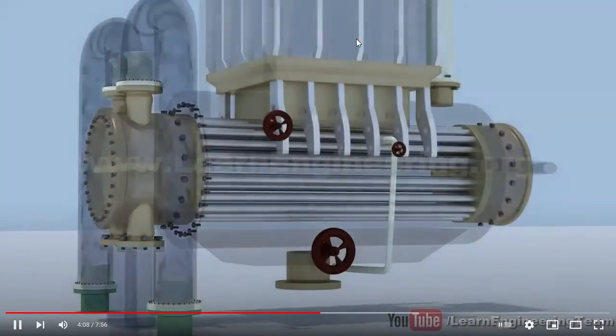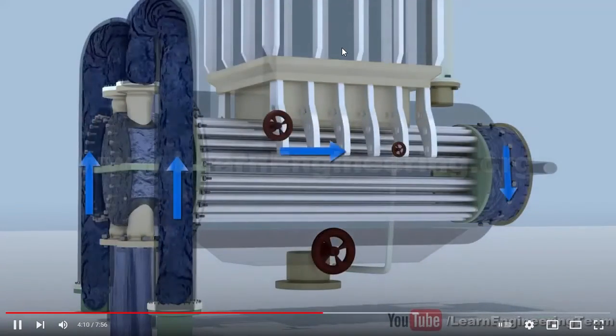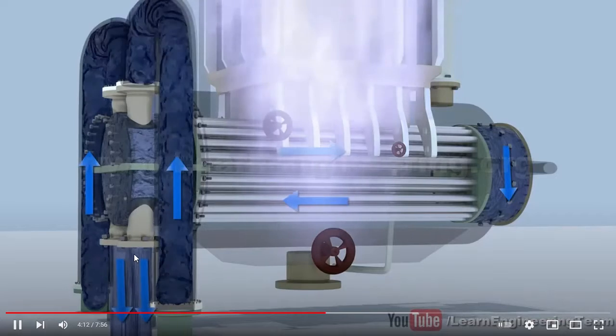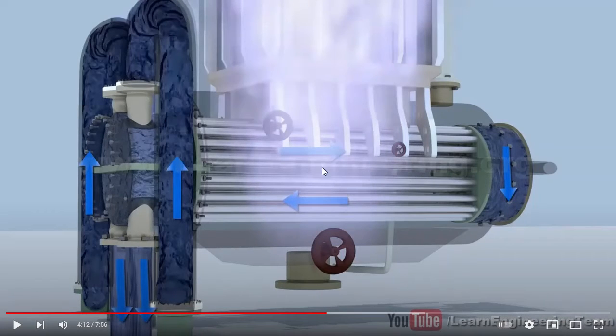So to do that, you'll see that steam pop up here in just a second. So the steam's coming down through there. That steam comes through here, like we talked about it. We've got these tubes in here. So inside the tubes is water from the cooling tower, right? Outside the tubes is steam, and those don't mix. In fact, it's really bad if they do mix. So we work really hard to make sure that the water inside the tubes does not get out of it.